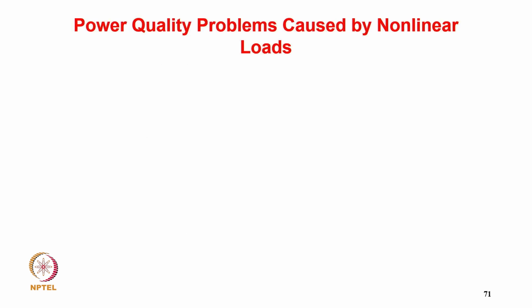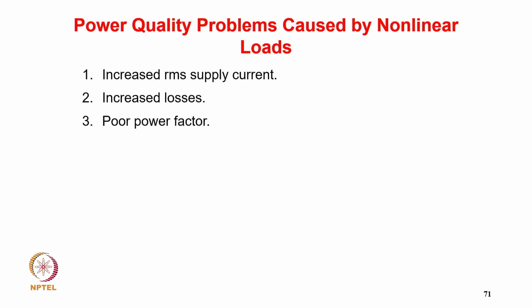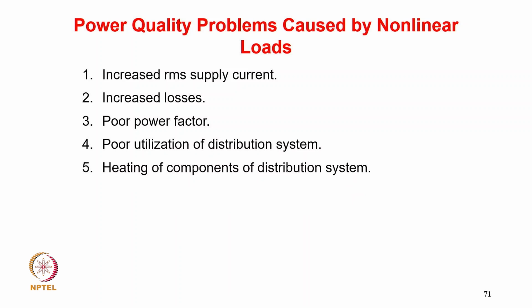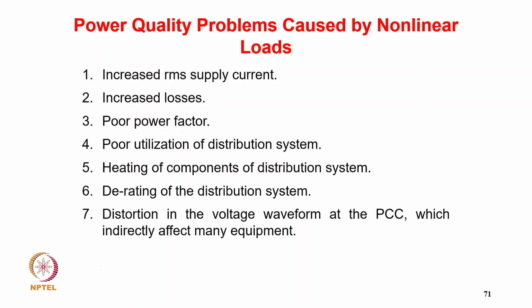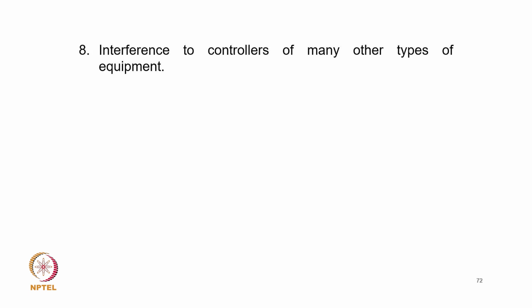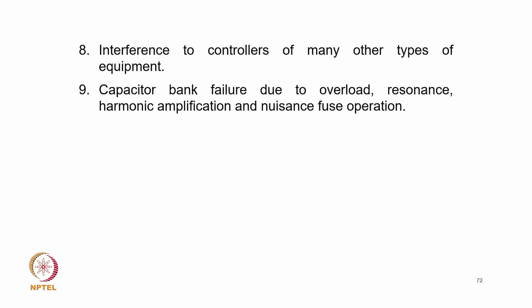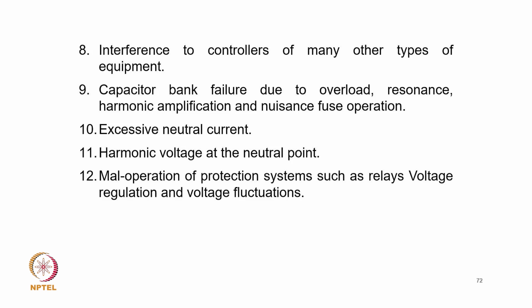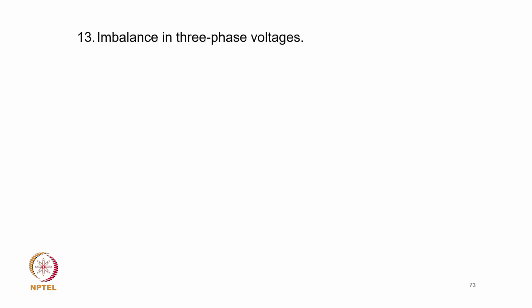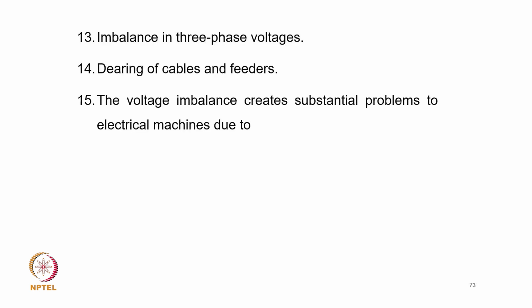Typical chemical, computer or electronic ballast loads cause power quality problems as non-linear loads, like increased RMS current, increased losses, poor power factor, poor utilization of the distribution system, heating of distribution components, derating of the distribution system, and distortion in the voltage waveform at the PCC, which indirectly affects many equipment and interferes with controllers of many other types of equipment. Also capacitor bank failure due to voltage resonance, harmonic amplification and nuisance tripping, excessive neutral current, harmonic voltage at the neutral point, maloperation of protection systems such as voltage relays, voltage regulation and voltage fluctuations, imbalance in the three-phase system, and derating of cables and feeders.